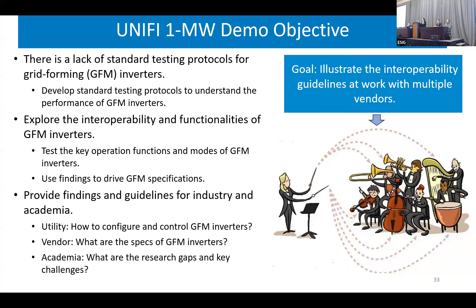I will start from the background of why we want to do this multi-inverter testing. As of today, there are so many grid-forming inverter testing protocols, but they're all for simulation — you can name the one from UK, from AEMO, FinGrid, and many others. There is no single testing protocol for hardware, so there's a gap there. That's why we want to develop a comprehensive, standard, and strict testing protocol for grid-forming inverters to address this gap.